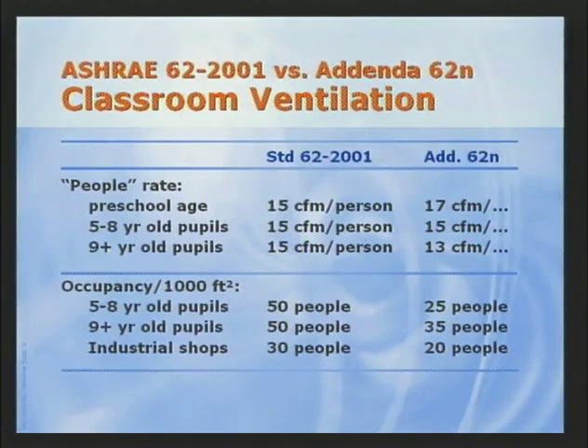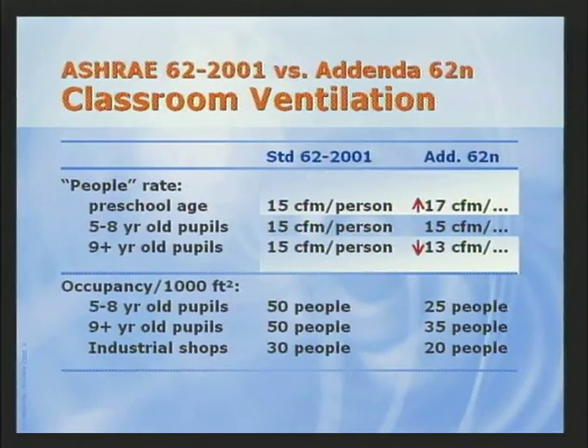However, classrooms for older children, 9 years old and up, went down to 13 CFM per person, while preschool areas increased to 17 CFM per person. It's also interesting to note that the previous version of the standard estimated classroom occupancy at 50 students per 1,000 square feet. That has been lowered to 25 for rooms with 5 to 8-year-olds and 35 for 9-year-olds and up.